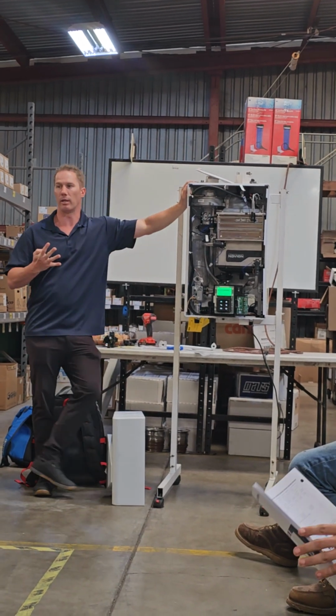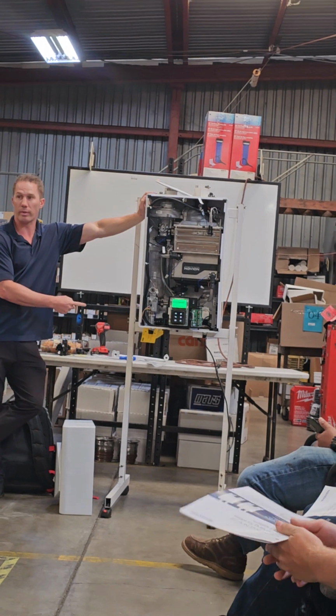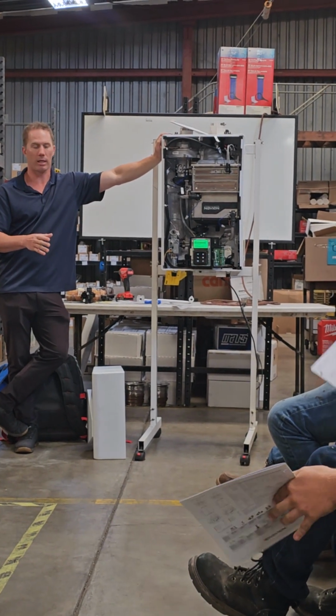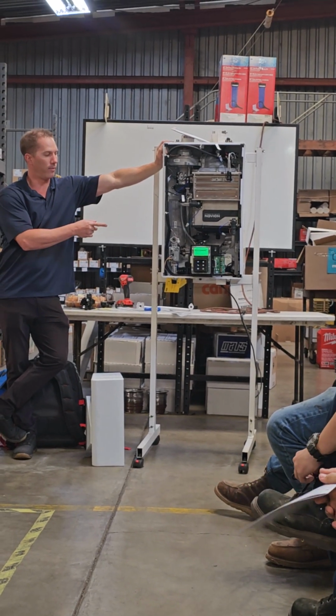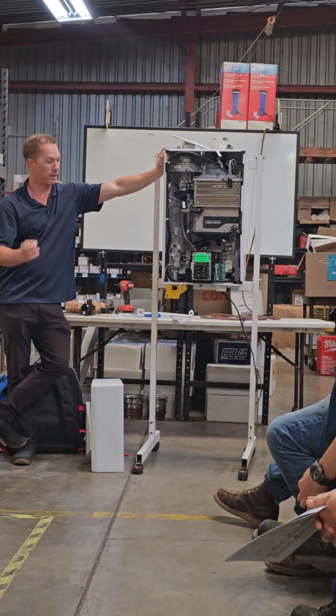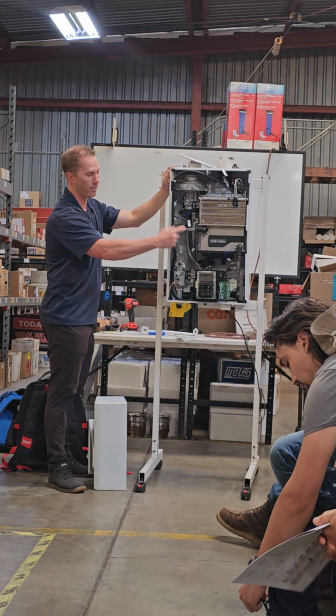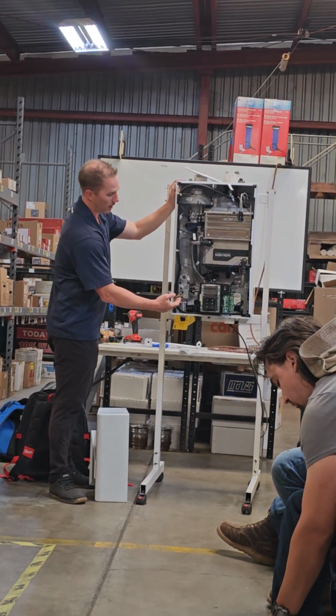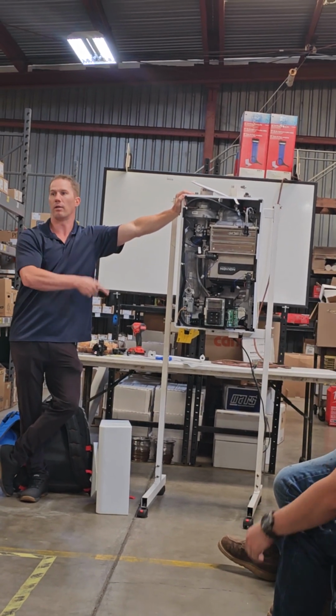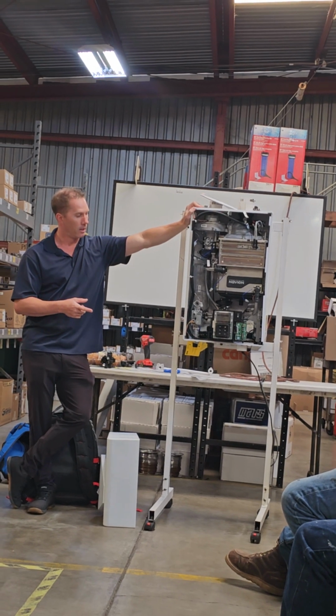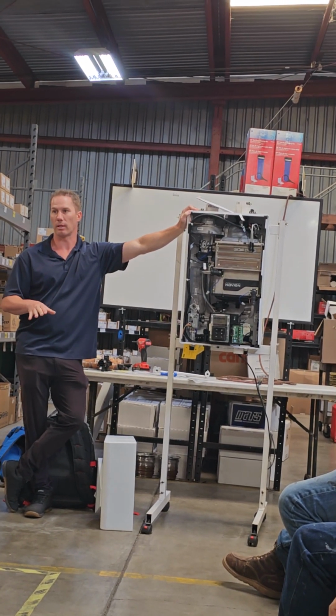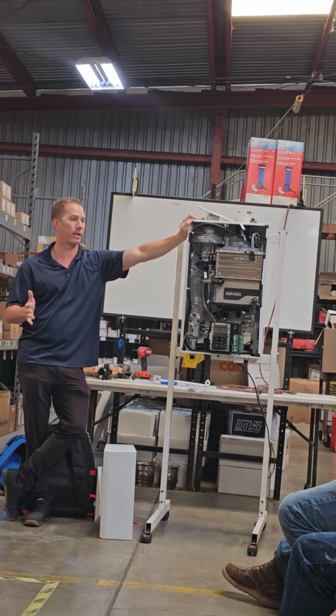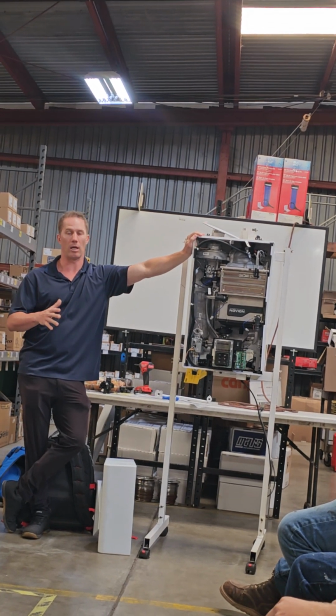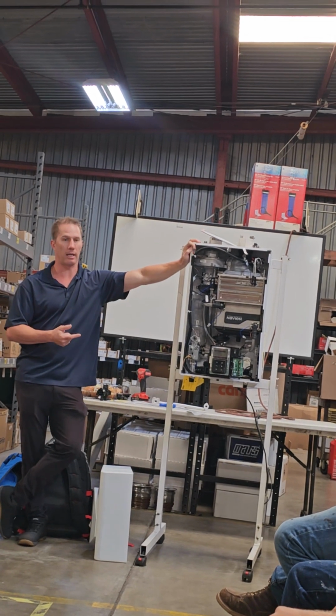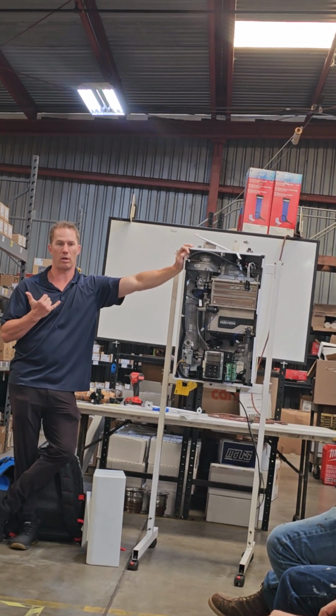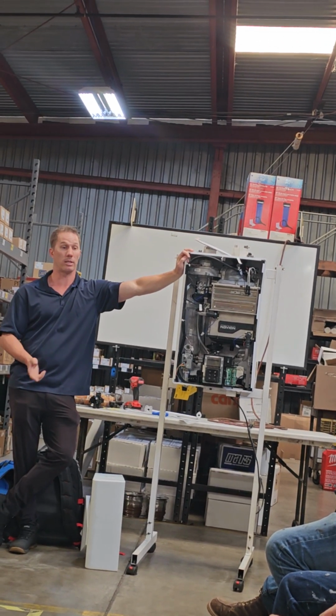There are 4 different ways to do it. First, always on: it samples the recirc line every half hour, 24 hours a day, 7 days a week. If it's 9 degrees colder than the set temperature—say it's set at 120—it kicks on the pump just to push water through the recirc line. If the recirc line is 111 or colder, it kicks the unit on and fills the entire hot water line with recirc. It does that every half hour, 24/7. Don't use that setting—always on is really meant for something like an old folks' home where they need hot water any time of day. If you put it in a propane install and set it to always on, the homeowner's going to call and be upset because it'll eat up propane, especially in winter, kicking on the recirc every half hour.